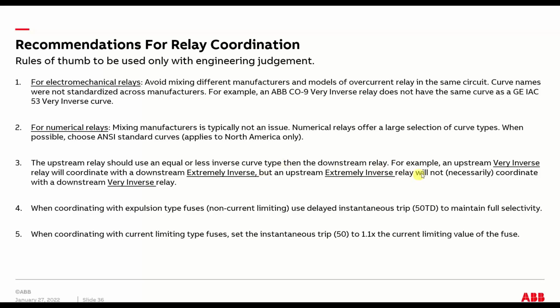But you can do, as long as your upstream stuff is less inverse, you're okay. So for an example, a very inverse relay upstream will coordinate just fine with an extremely inverse relay downstream. But the opposite's not true. So an extremely inverse relay that's downstream will conflict with a very inverse relay that's upstream. So rule of thumb is to try to keep them all the same curve type when applicable and possible. And if not, always have your less inverse curve upstream.